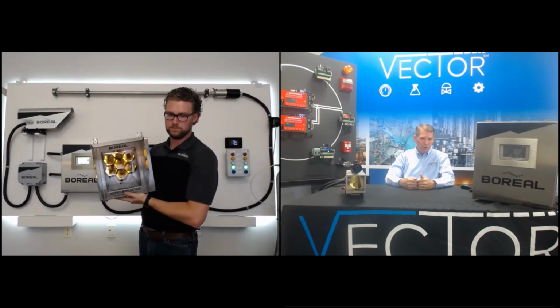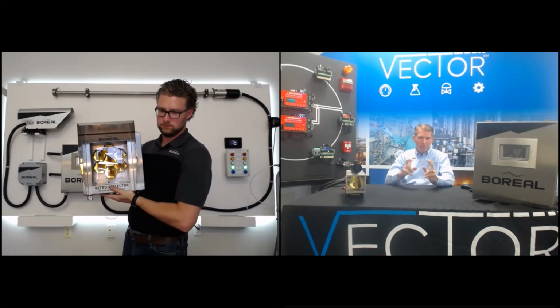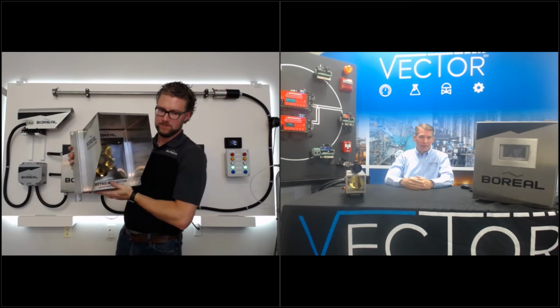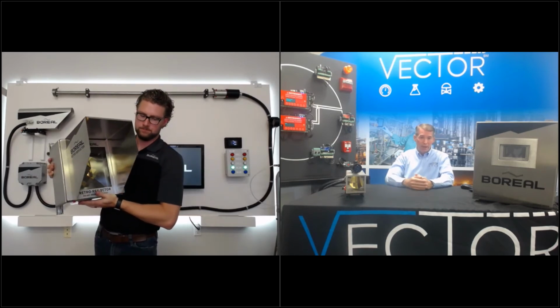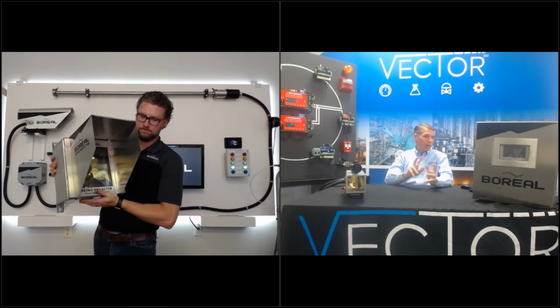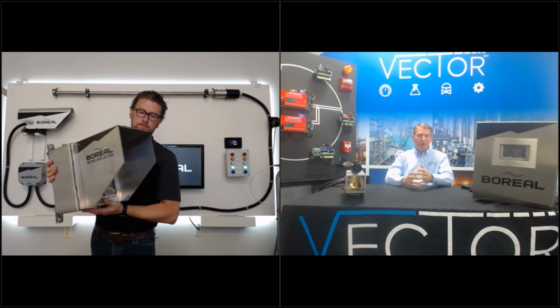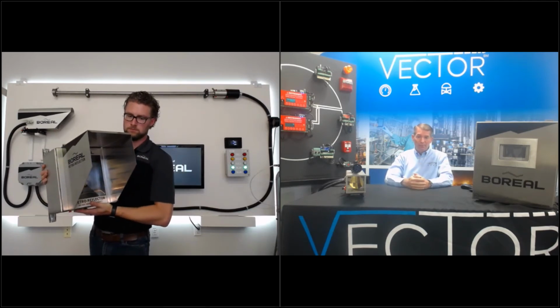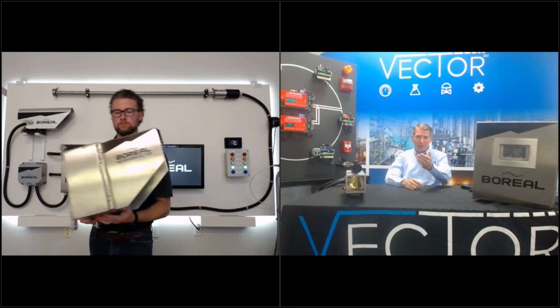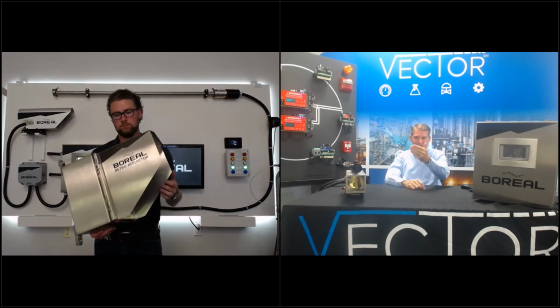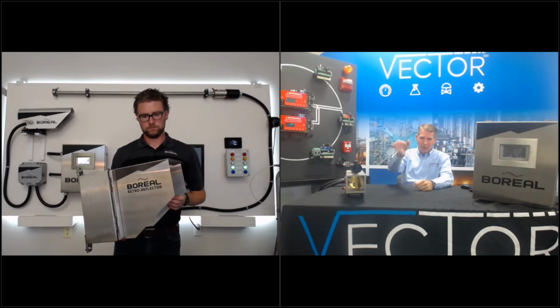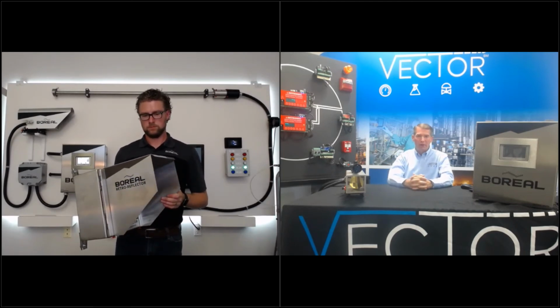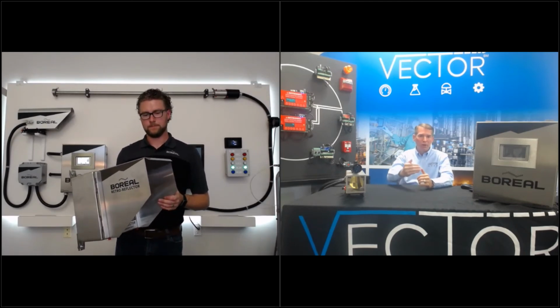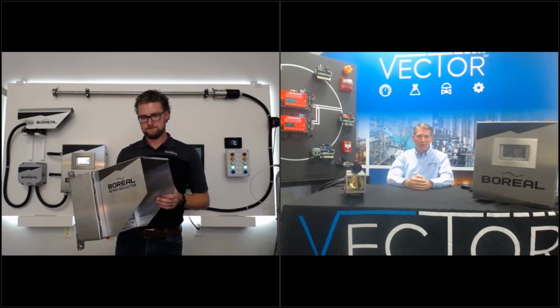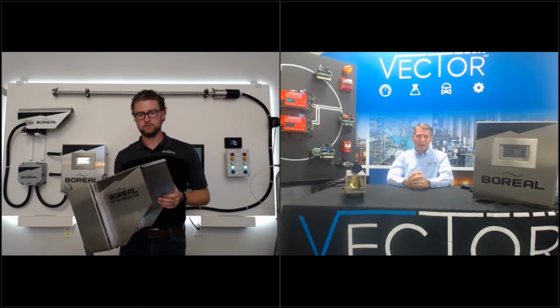And if for any reason something were to coat the window and dry, it would be the same thing as a beam block or dirty optics indication, right? So you would just simply go and clean the window gently. But typically, Kyle, you can correct me if I'm wrong, nothing really sticks to that window because of the protection and because of the angle of the window itself. But it will give you an indication, like we said earlier, that if it can't see, it will tell you.